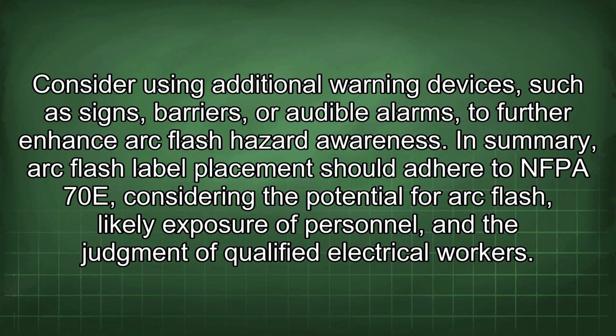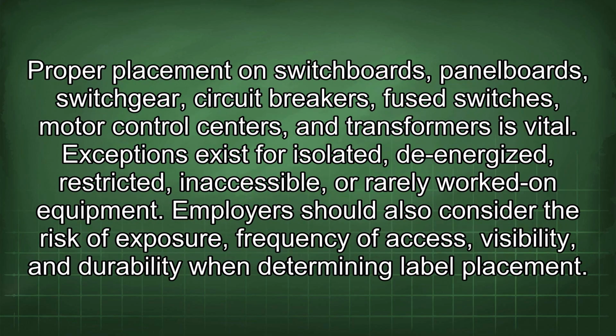In summary, arc flash label placement should adhere to NFPA 70E, considering the potential for arc flash, likely exposure of personnel, and the judgment of qualified electrical workers. Proper placement on switchboards, panel boards, switchgear, circuit breakers, fuse switches, motor control centers, and transformers is vital. Exceptions exist for isolated, de-energized, restricted, inaccessible, or rarely worked on equipment.